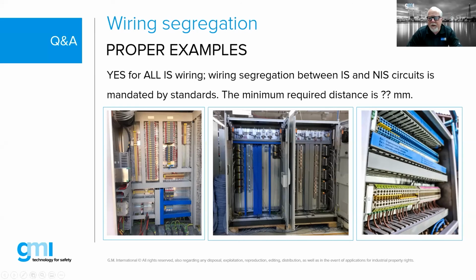But here's the other thing. People, that's obviously inside of the panels, excuse me. But then you also have to be concerned about the cables that are running into your panels, right? Mm-hmm. So we have to make sure that we keep a 50 mm separation between IS and non-IS cables exterior to our panels, unless, and this is an important point to remember, we can separate them by the use of partitions inside of cable trays.